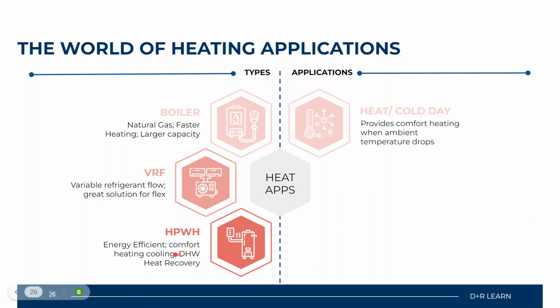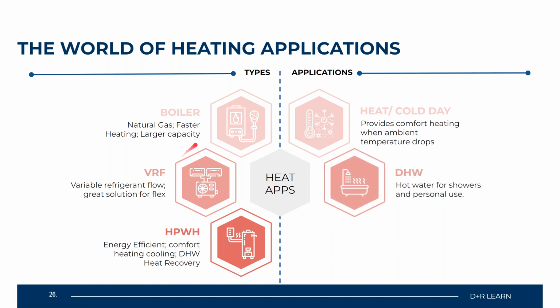Oh, and I just wanted to mention here with the heat pump systems as well, you can have a heat pump system provide comfort heating to your residents if you have that option present or you would like that option within your cooling application. So the applications the heating types would be suitable for are heating on a super cold day or providing comfort heating when your ambient temperatures drop below, let's say, 33 or 32 degrees Fahrenheit. So we are able to stay comfortable inside of our homes or working spaces because we have the ability to turn these systems online. We also have the ability to create domestic hot water for showers and also personal use.